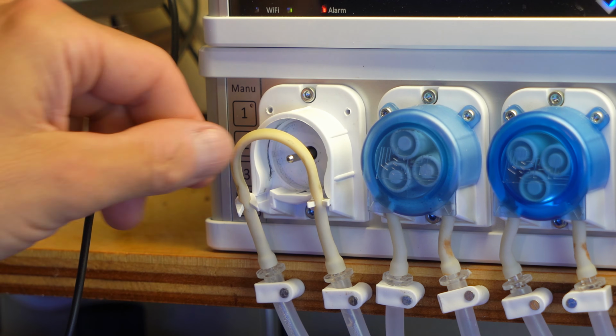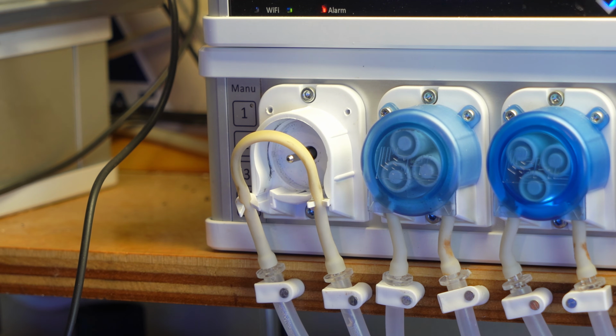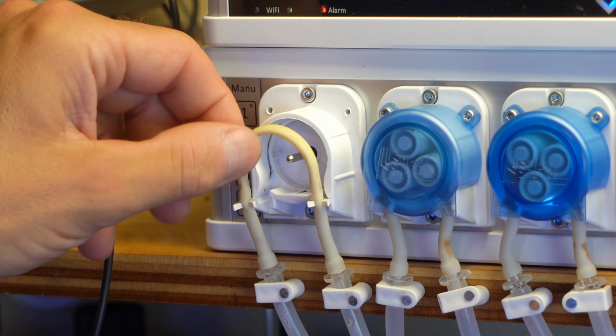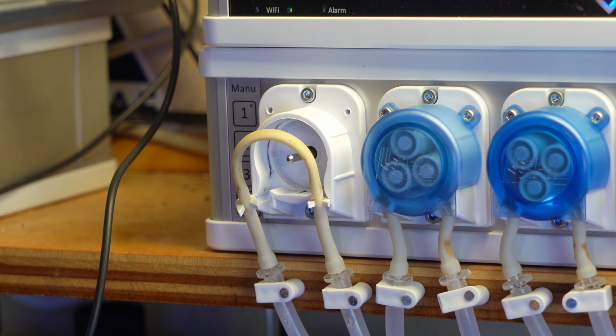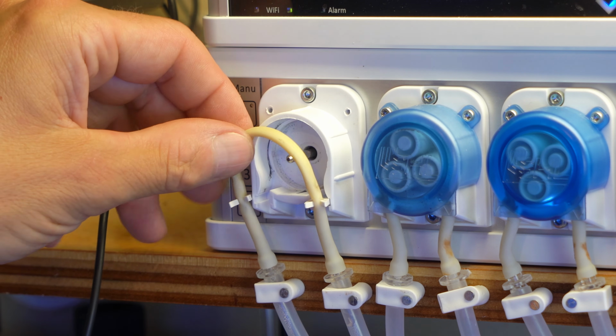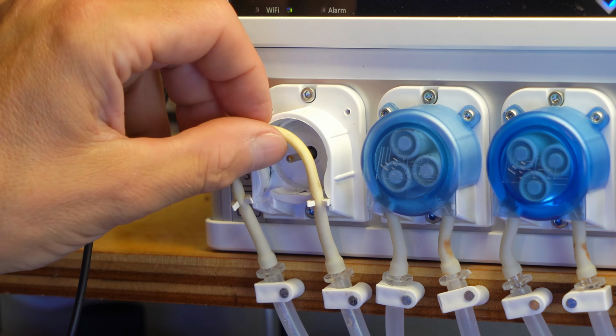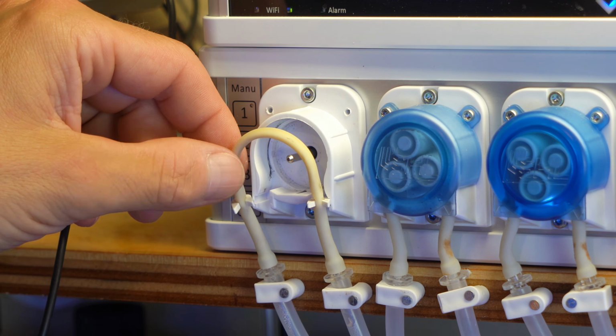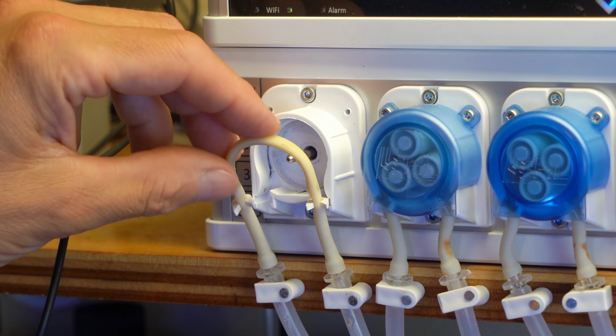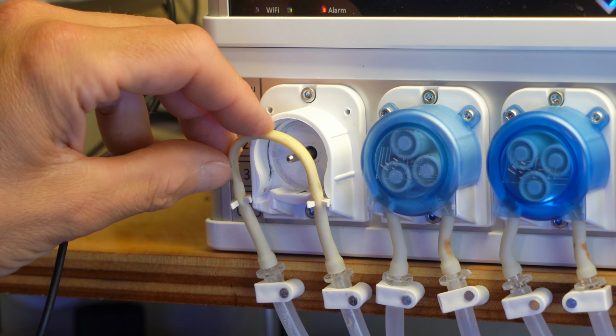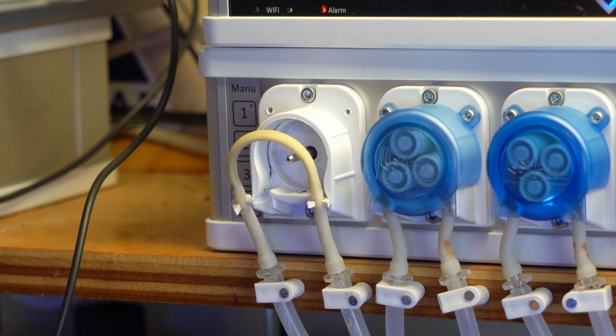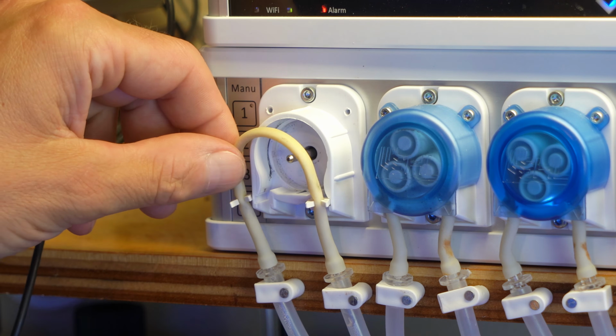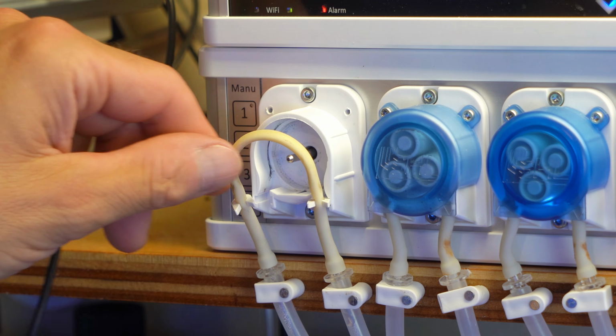The silicone tubing is a part that sometimes, not too often, needs to be replaced—it depends on how often it's used and the wear and tear. I did have a situation once where I was using a dosing head very frequently, dosing a lot of liquids, and the pump just stopped working. There was a micro fissure in the tubing, and replacing the silicone tubing fixed the problem. So always be aware of this, and I suggest having some spare silicone tubes on hand, as well as rollers and the cap. There are replacement parts for all of this—there's a GHL Doser maintenance kit as well as separate silicone tubing. I'll leave links in the video description below for all this stuff if you need it.